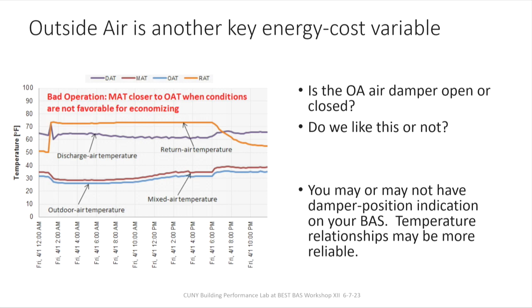Okay, I'm a little nervous, but I feel like since the mixed air temperature is trending so close to the outdoor air temperature, that was the biggest indicator to me that even though the return air is coming back above 70, when it mixes with the outdoor air, it trends pretty close to that outdoor air temperature, which would indicate it's mixing with a lot of outdoor air. Absolutely correct.